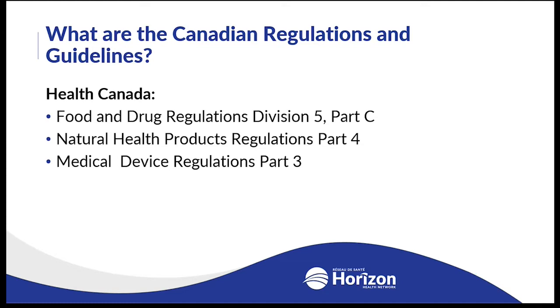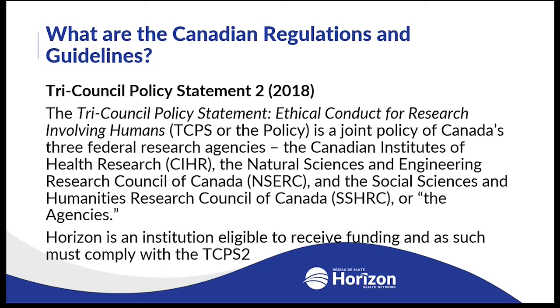The Canadian regulations and guidelines we are subject to include Health Canada's Food and Drug Regulations Division 5, Part C; the Natural Health Products Regulations Part 4 for investigational trials with natural health products; and the Medical Device Regulations Part 3. For international trials, we are also subject to FDA US regulations, which we'll discuss further.